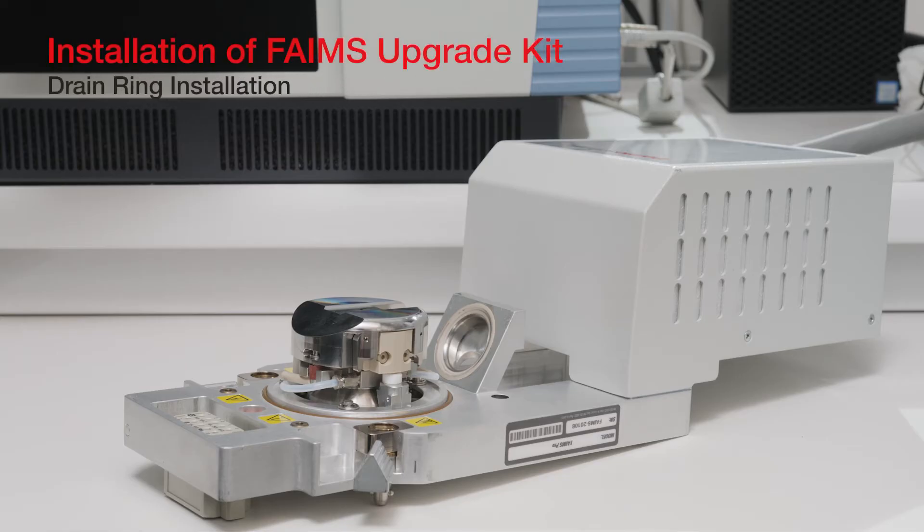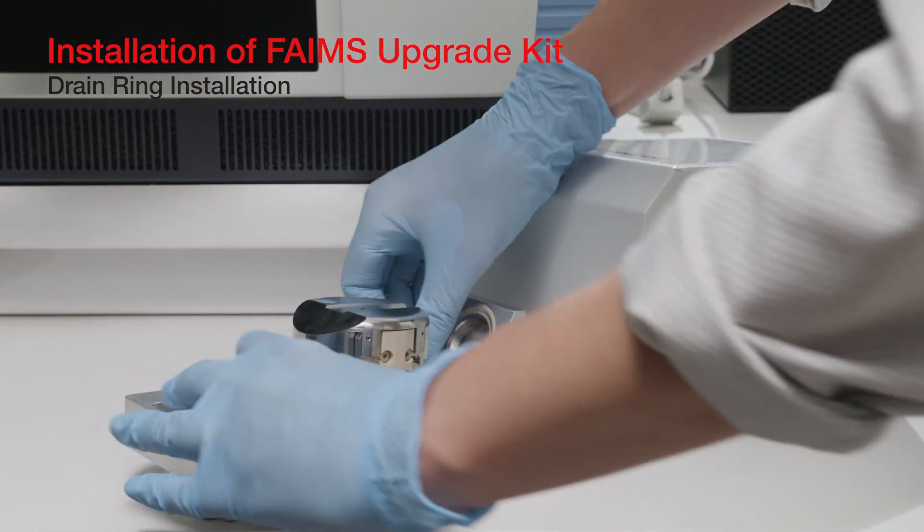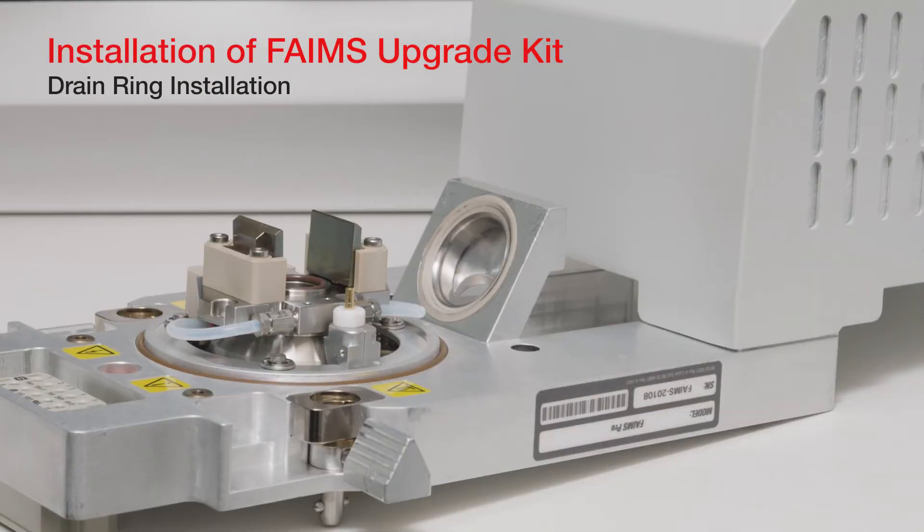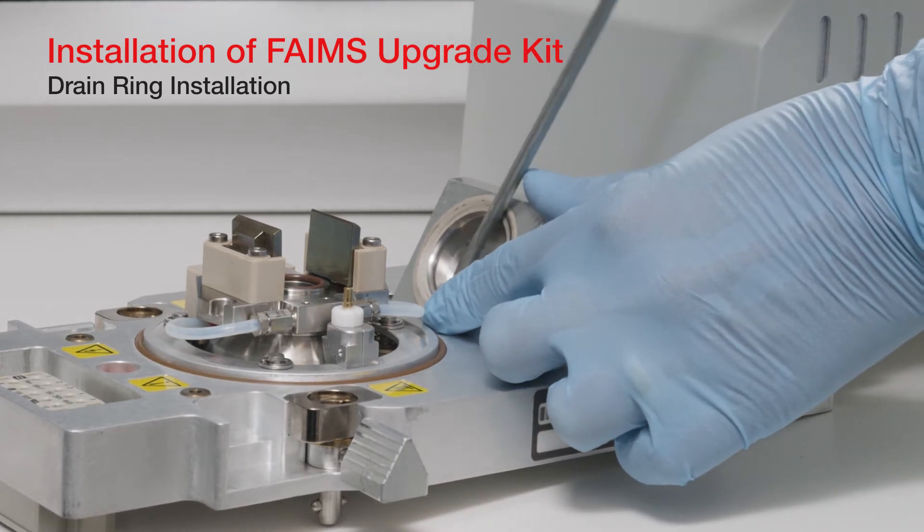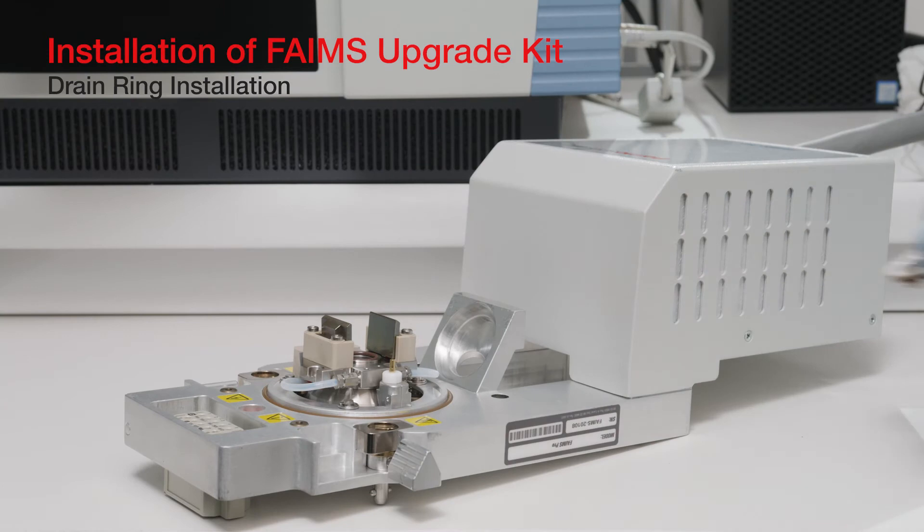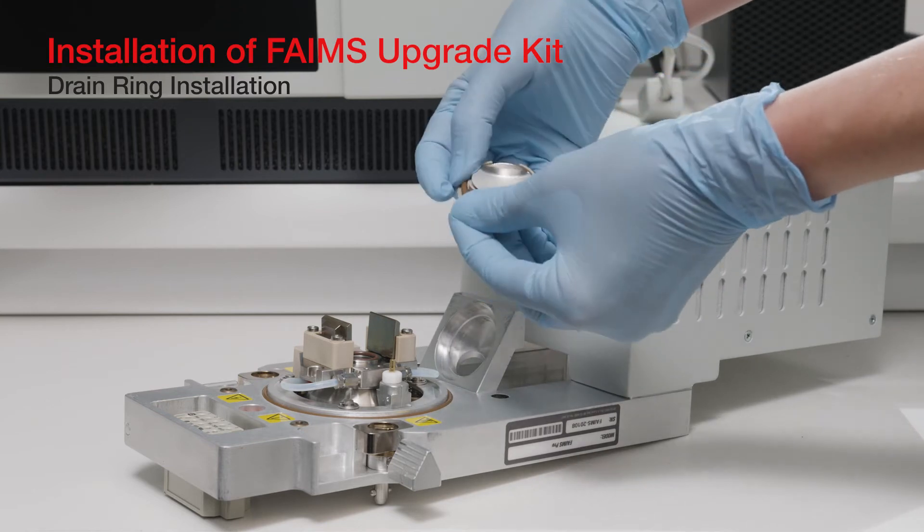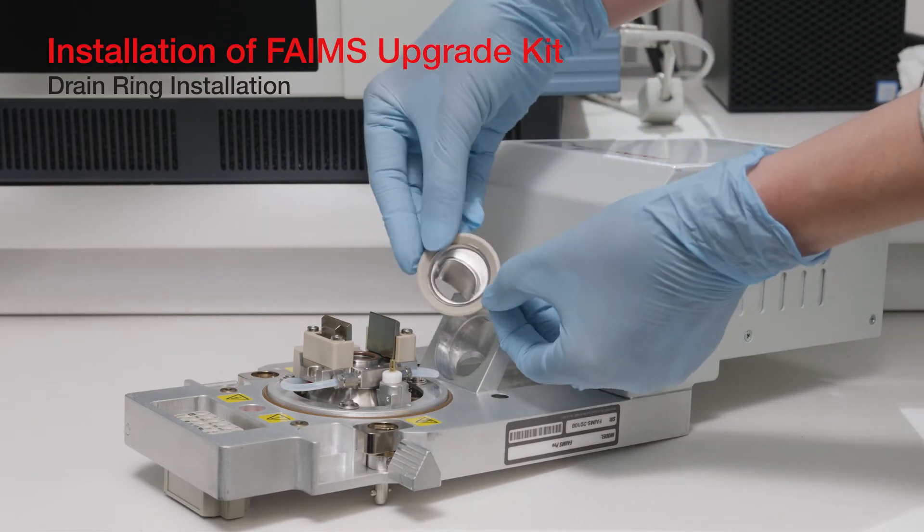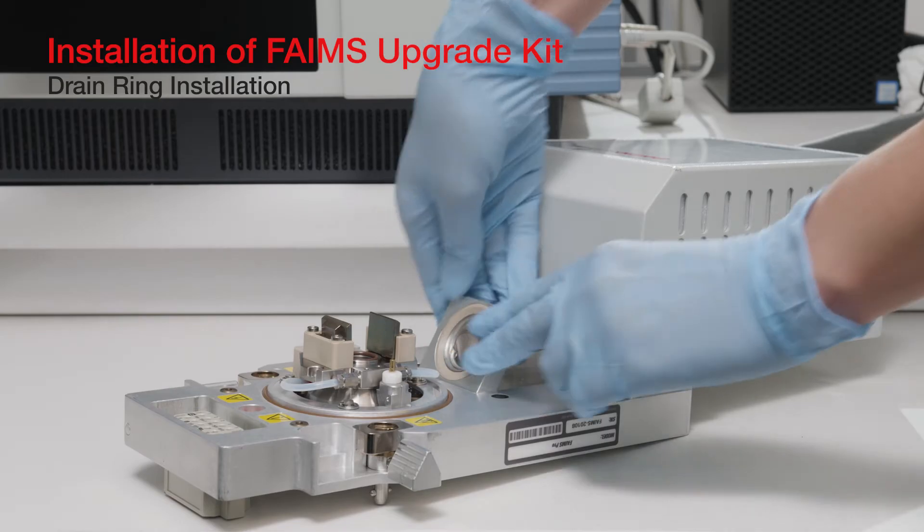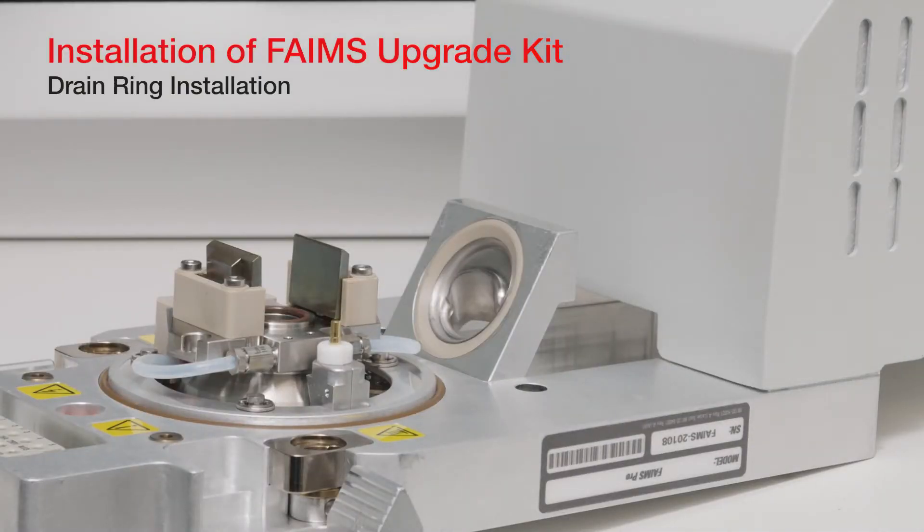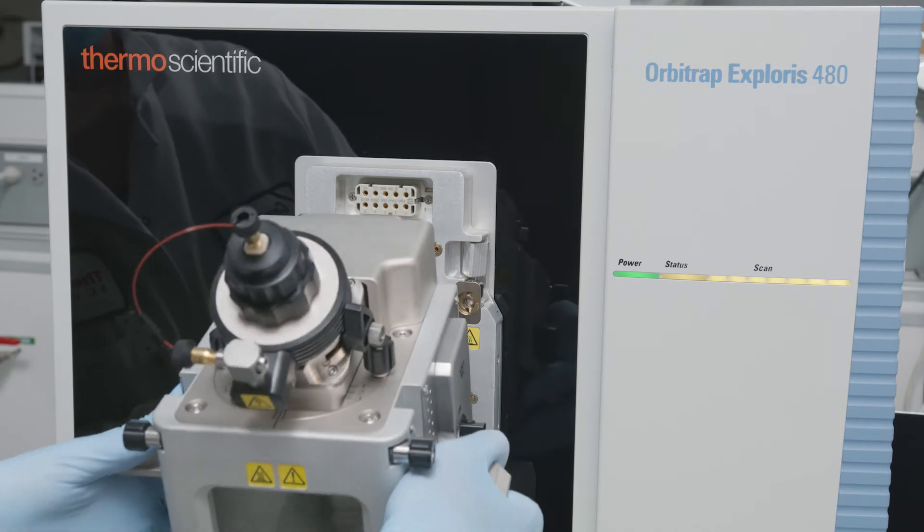Remove the FAIMS Pro from the MS and place the housing adapter module on a flat surface with the electrode assembly facing up. Remove the electrode assembly from the FAIMS Pro to gain easier access to the drain ring. Insert the small flathead screwdriver between the drain ring and the housing adapter, and gently pry the drain ring from the housing adapter. Then place the O-ring on the bottom of the FAIMS Pro Duo drain ring. Align the FAIMS Pro Duo drain ring with the housing adapter such that the bottom side of the O-ring faces down towards the RF box. Push the drain ring in place until it sits flush with the housing adapter.